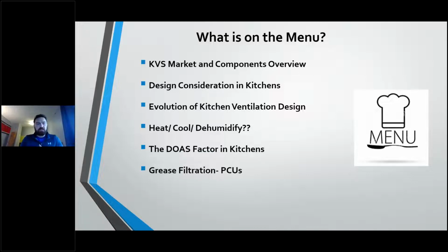So what that all comes into play is the age-old question in the kitchen: do we heat this air? Do we cool this air? Do we dehumidify this air? How does a standard dedicated makeup air system, regardless of manufacturer, fit into that system? And now we're seeing more DOAS units, or dedicated outdoor air systems, coming into kitchens that are going to allow for dehumidification. So what are we seeing across the country?